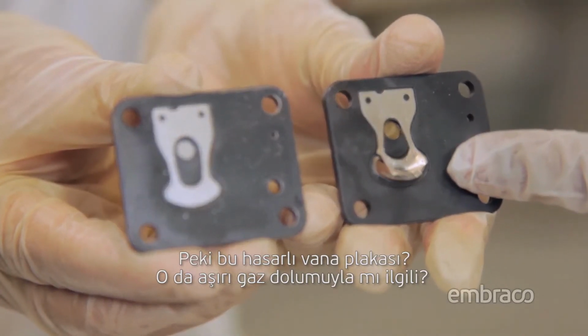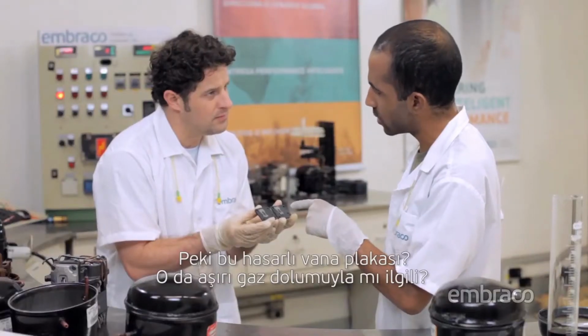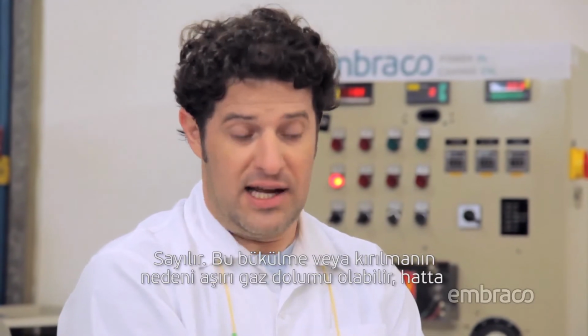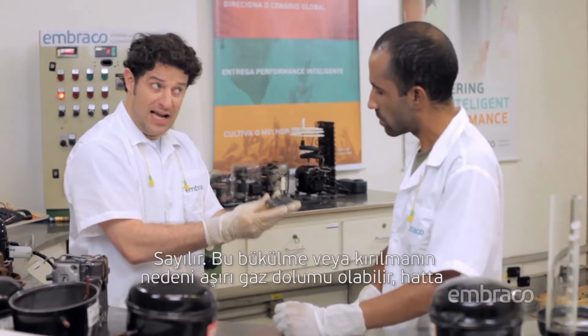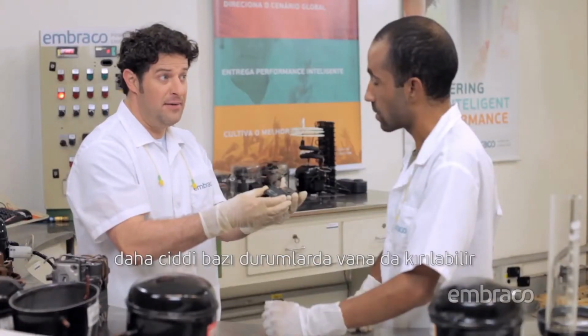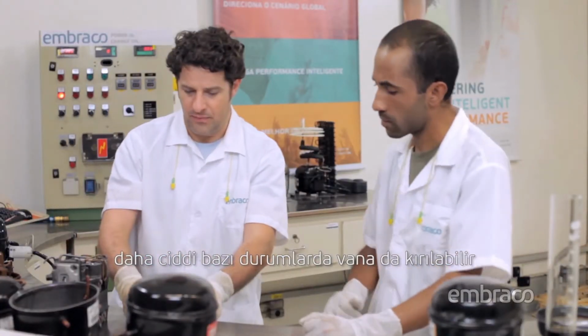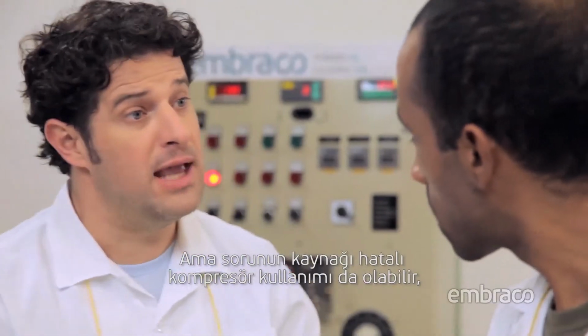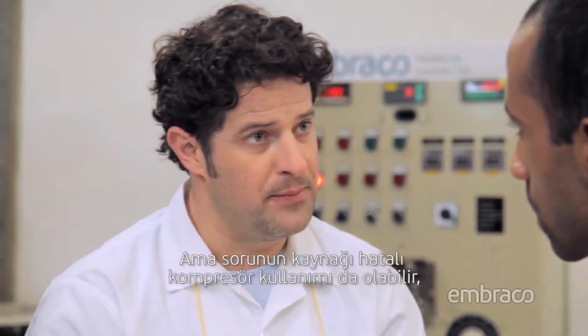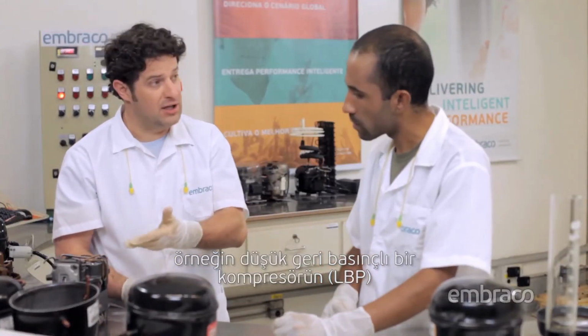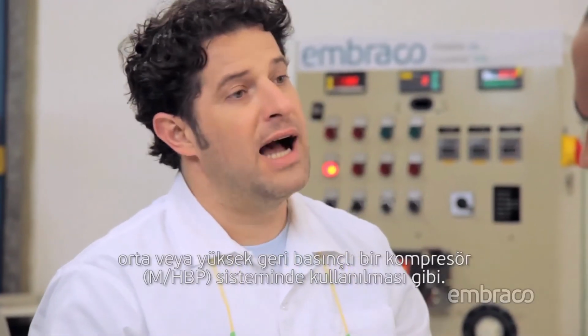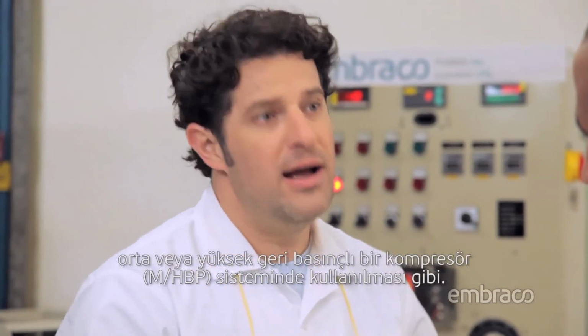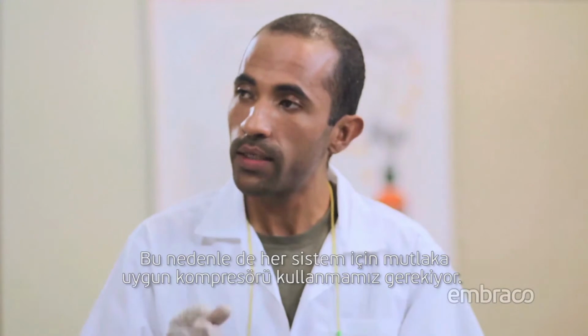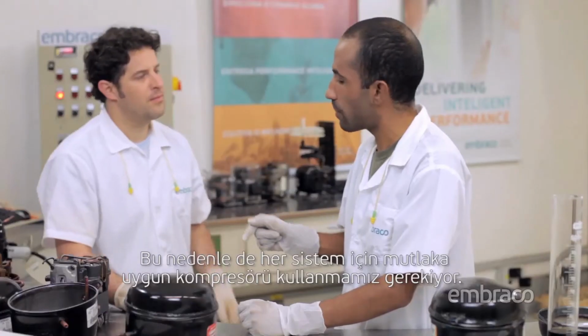In this damaged valve plate, is it related to excess gas charge? That's it. This warping or breakage may be related to excess gas charge, and in some more severe cases, the valve can break. But it might also be the incorrect compressor used. For example, a low back pressure compressor, LBP, being used in the system for medium or high back pressure, MHBP. Oh, for this reason, it's important to always use the suitable compressor for each system.